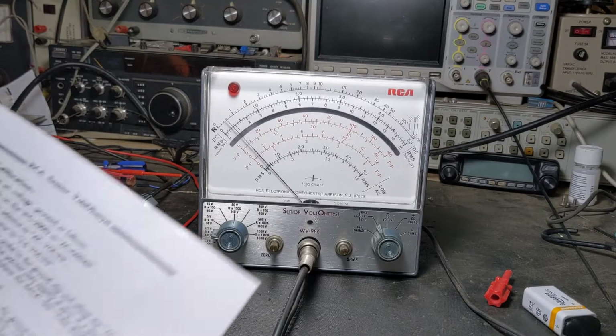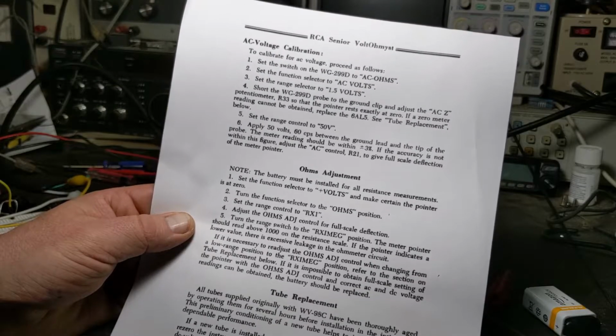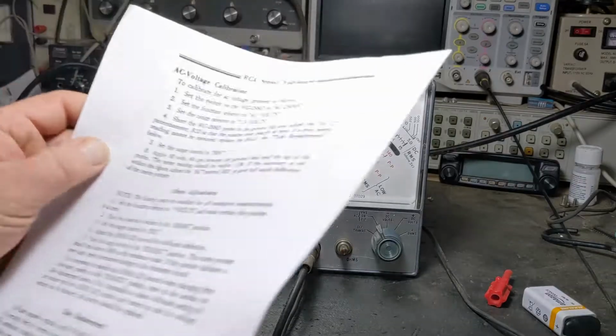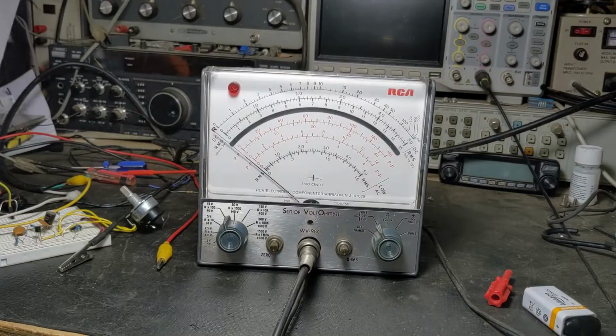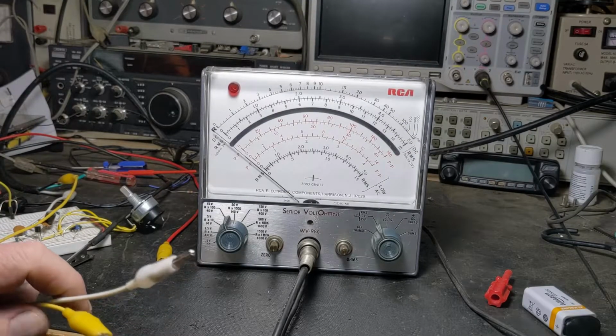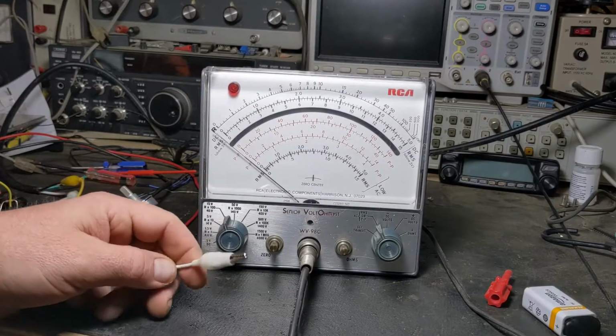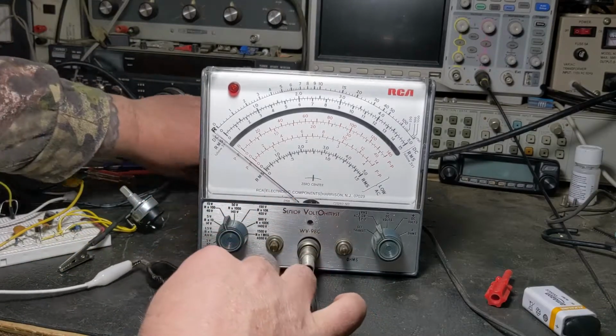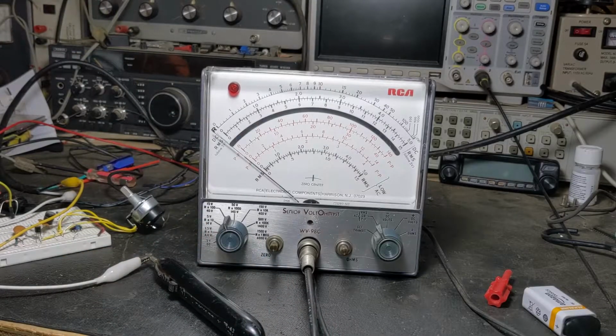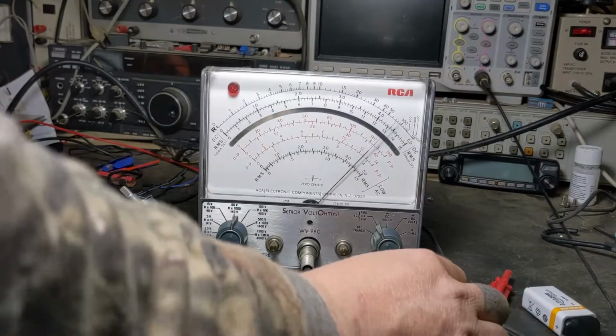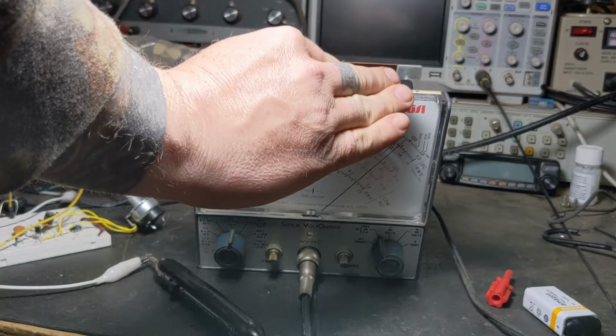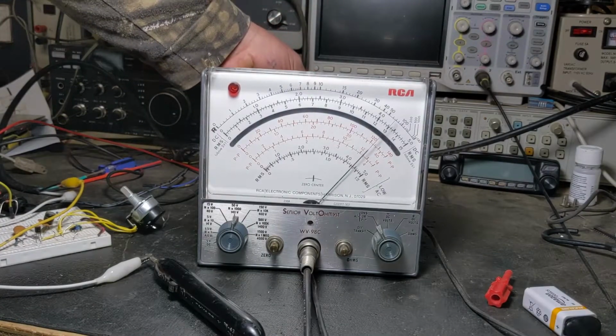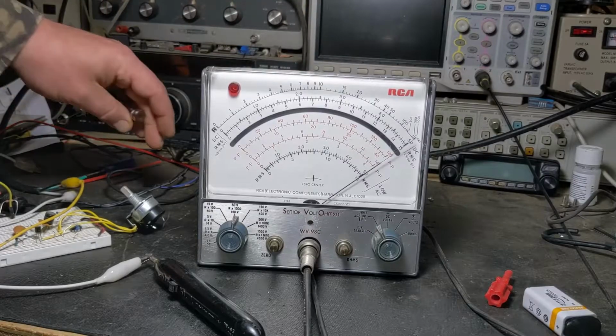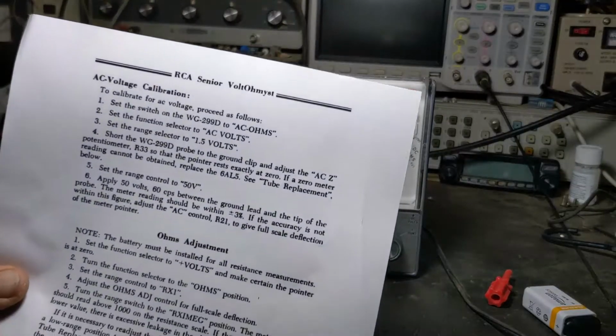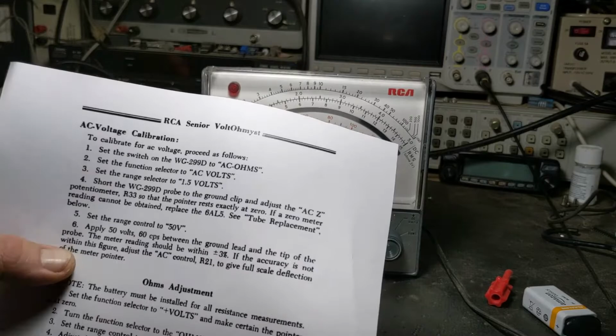And it may go off of it a little bit when you take it loose, but don't worry about that. Now, set the range switch to 50. And apply 50 volts. Okay. And I've got that set up here too, very carefully. On a different supply. I'll let that hang there. Set that there. Touch that. Everything looks okay. I don't know if it'll go to 50. Turn that on. Okay. Now we're going to adjust the AC. So, there we go. Turn that off. And that takes care of setting the 50 volts, or the AC section.